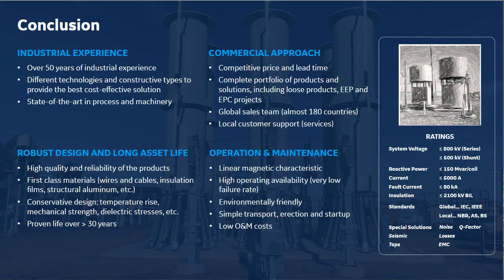Is there any voltage level limitation for shunt reactors? Meaning, are 245 kV and 145 kV levels also required to be the same, or do we only install in 500 kV systems? I think the question is, for shunt reactors, called dry type, is there a voltage level limitation? The answer today is yes, there is a voltage level limitation, which is around 500-550 kV, which is already very high. So air core dry type today covers basically all the voltage levels available. Of course, 765 kV or 800 kV would still require the traditional oil-filled design.